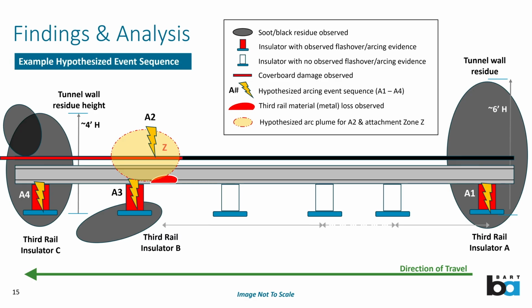Starting with the yellow oval, there was damage noted to the top of the cover board consistent with damage occurring from the top down, from an initiating source. We also see a characteristic soot deposition pattern behind the insulator when it fails, usually aligned with it. In this case we saw it at location A and at location C.